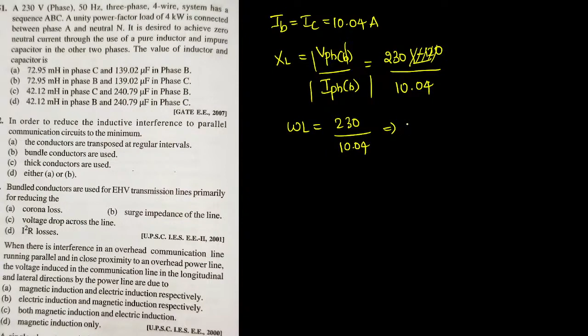Similarly, capacitor for phase C. Phase C, magnitude is 230 as usual. Current is same because phase B and phase C currents are equal. From this, the value of XC can be written as 1 by omega C equal to 230 divided by 10.04. From this, omega C equal to 10.04 divided by 230. From this, C is equal to 10.04 divided by 314 into 230. That is the value of capacitor.